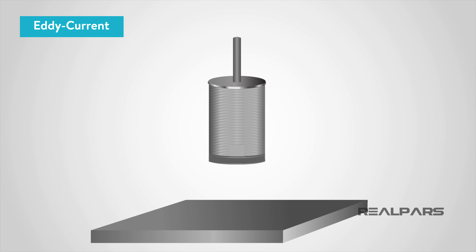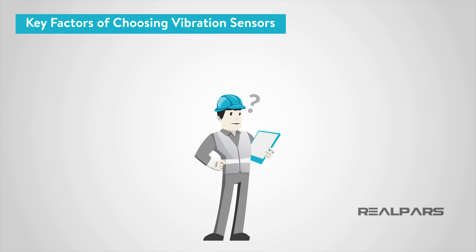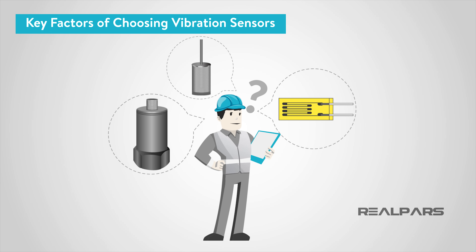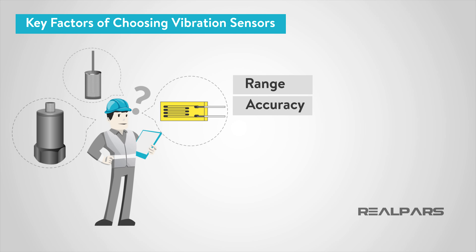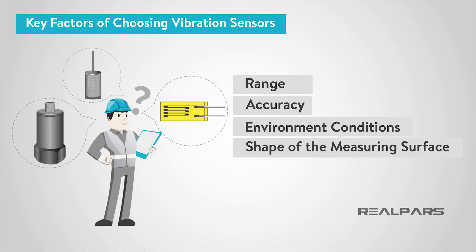When using eddy current sensors, it's important for the component to be at least three times larger than the sensor diameter for normal operation. Otherwise, advanced calibration would be required. When choosing a vibration sensor for your application, it's important to look at factors such as range and accuracy, environmental conditions, and the shape of the measuring surface.